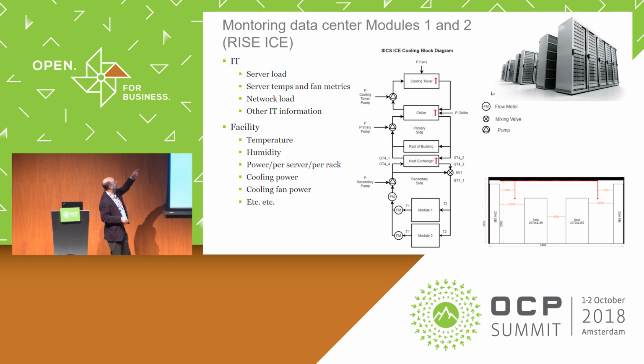We have a lot of IT equipment being monitored in the facility, so we can check the cooling power going into the modules. You've got the water loops here. We're in a cold storage facility, so we have compressor-based chilled water loops which we tap into through a heat exchanger. Although we don't have control of the final heat rejection, we do have control of the temperature to the pods, because we're on a separate loop from the cooling loop.